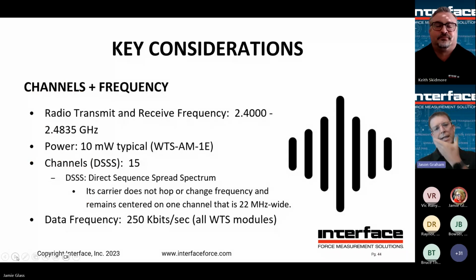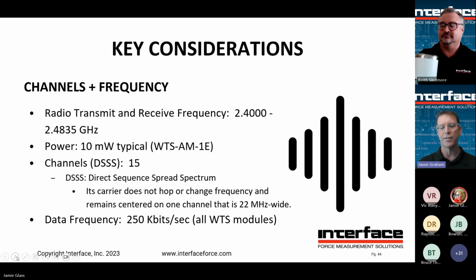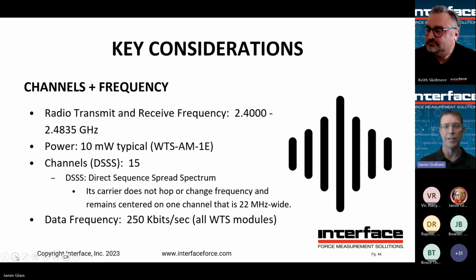When you look at key considerations around channels and frequency - wireless is in the 2.4 gigahertz range, so 2.4 to 2.4835. Most of the wireless modules have about a 10 milliwatt typical transmit power, and about 15 channels. When you look at these spread across the channels, the WTS toolkit does allow you to see how much saturation is at certain channels within certain frequency ranges, so that's kind of handy.